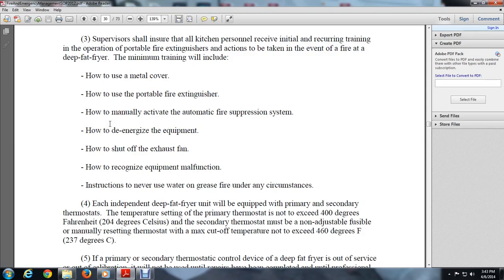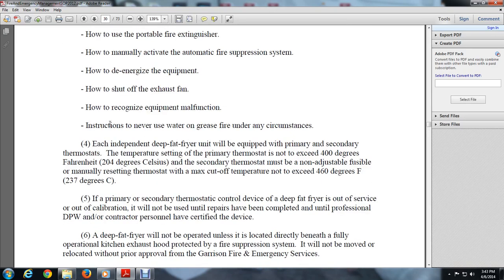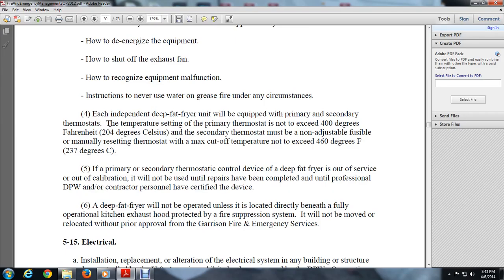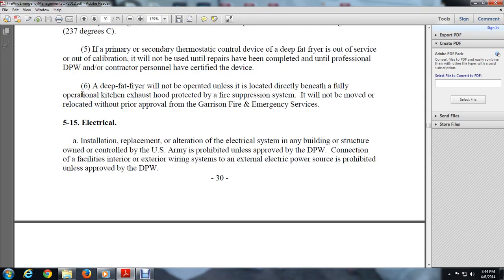The primary thermostat temperature must not exceed 400 degrees Fahrenheit or 204 degrees Celsius. The secondary thermostat must not be adjustable. Use a manual resetting thermostat with a maximum cutoff temperature not exceeding 460 degrees Fahrenheit, 237 degrees Celsius. 5. A deep fat fryer whose primary or secondary thermostat control device is out of calibration will be taken out of service and not returned until repairs are completed by professional DPW contract personnel who have certified the device. 6. A deep fat fryer will not be operated unless it is located directly beneath a fully operational kitchen exhaust hood protected by a fire suppression system. It will not be moved or relocated without approval of the Garrison Fire Emergency Service.